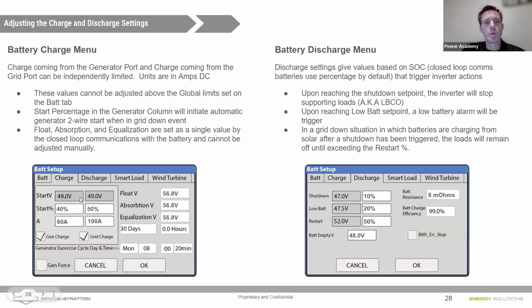You can do either, but with the 6.6 communicating battery, if you've enabled the communications, it will automatically select the percentage. You'll also note that you don't need to program the float, absorb, and equalize settings. Those will automatically be set by a communicating battery. If you're using the battery in open loop mode, or really best practice is to go through and set these values to the values they should be with communications disabled, and then come back through once you've plugged in communications, and it'll automatically be set. And that way, if you ever have any issue where communication drops, maybe something happens and communication stops working, it will still go to the correct values. So we can set both of those.